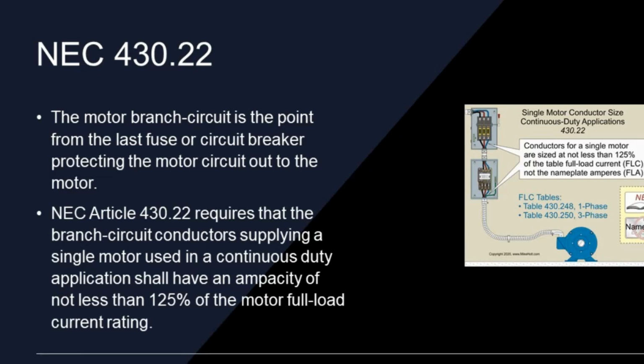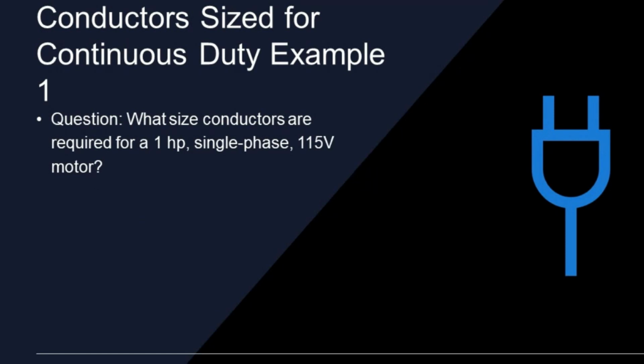Okay? So that means if I have a continuous duty application, which almost all your answers are going to have to be, this 125%, I don't care if it's this or your journeyman's test or where you're at. I've always seen them add the continuous duty 125% for conductors. So we're going to take that FLC number and we're going to multiply it by 125%, and that's how we're going to size our conductors. It's really that simple. So here we go. What size conductors are required for a 1 horsepower single phase 115 volt motor?